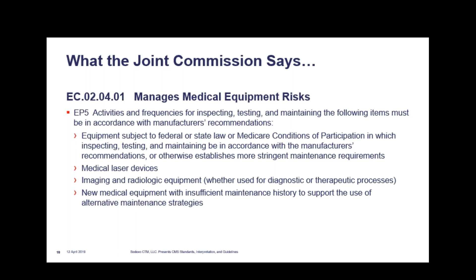CMS considers that AEM hospitals may, under certain conditions, use equipment maintenance activities and frequencies that differ from the original equipment manufacturer. An AEM program must be based on generally accepted practice, standards and practice for facility and medical equipment maintenance. AAMI, ANSI standard 56 and EQ 56.